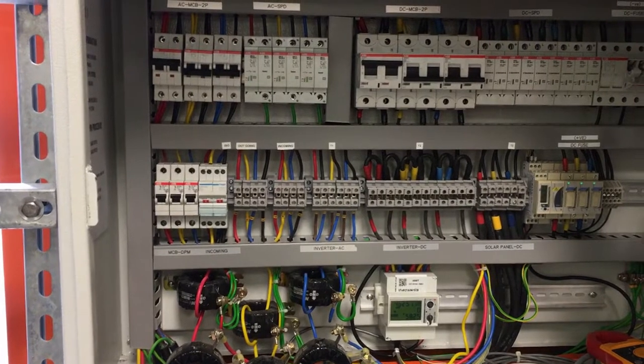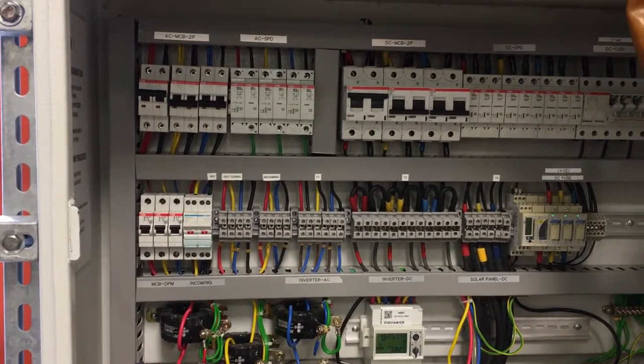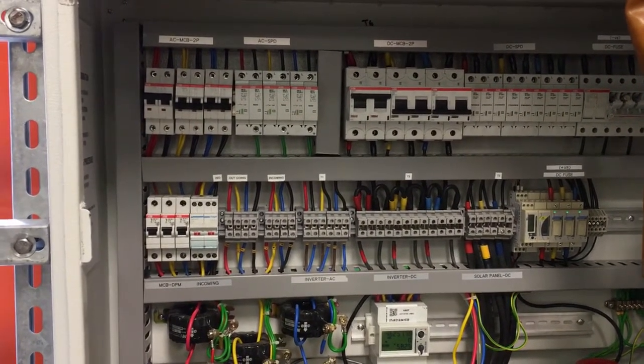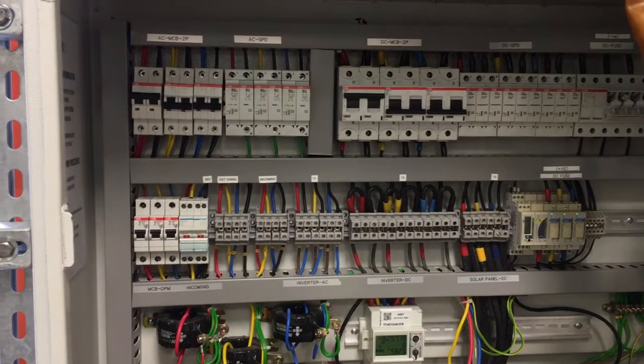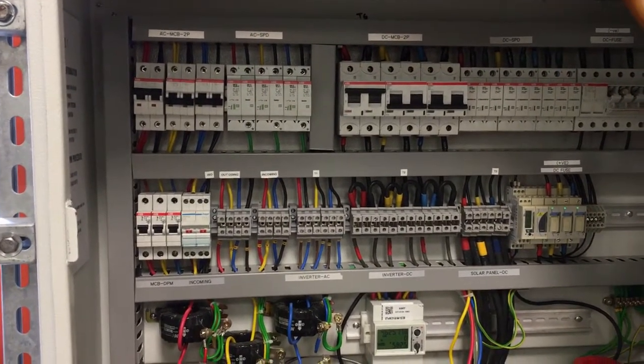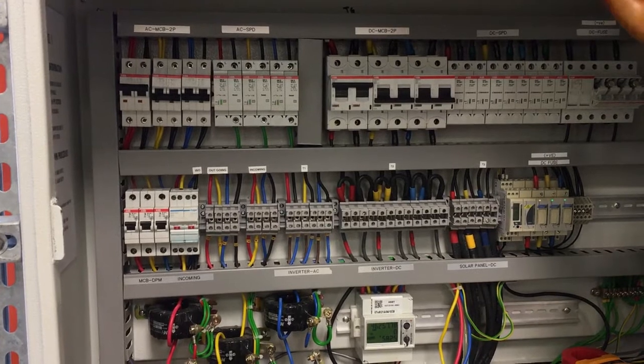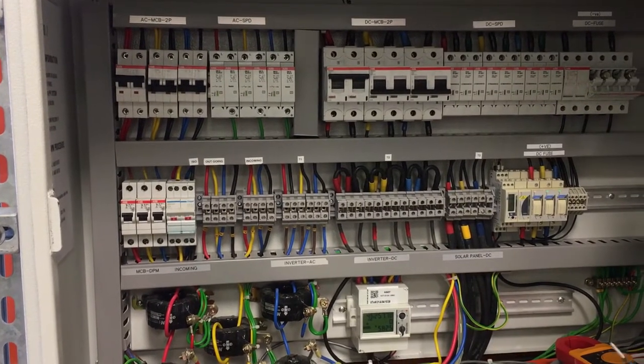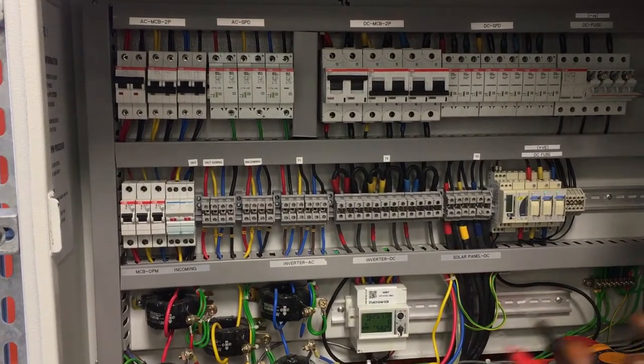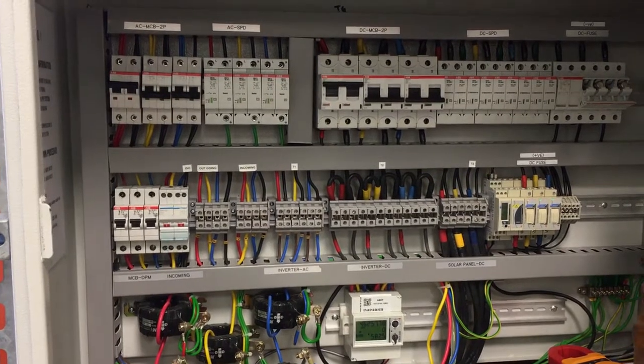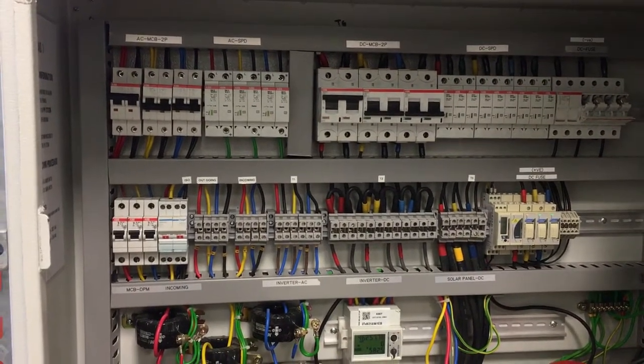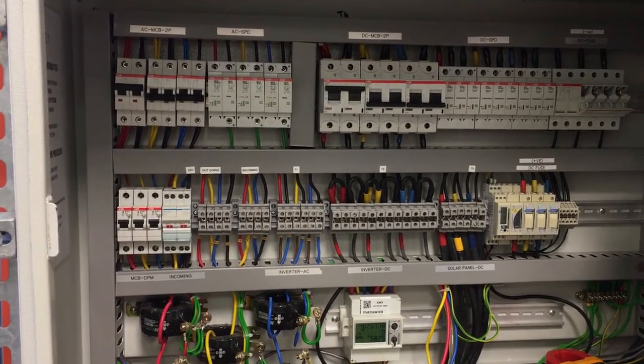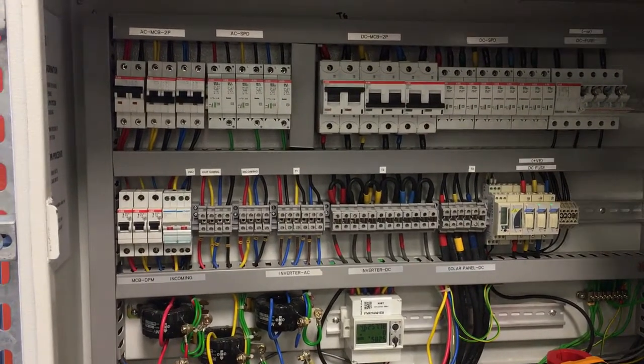So the sound that you hear is the sound of the inverter synchronizing itself with the grid. So it's going to check the value of the voltage and the frequency of the grid. If it matches, then it will connect the inverter. If it does not match, then it will not connect with the grid for safety purposes. Alright, so now if you move back and you see the inverter data or the inverter display.